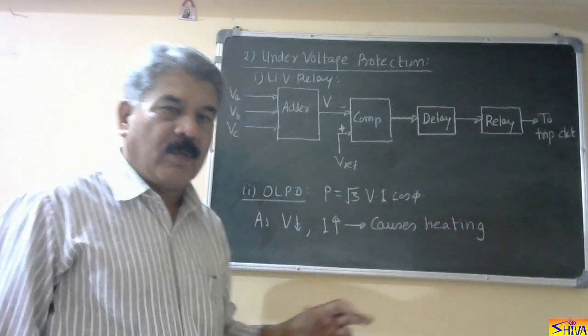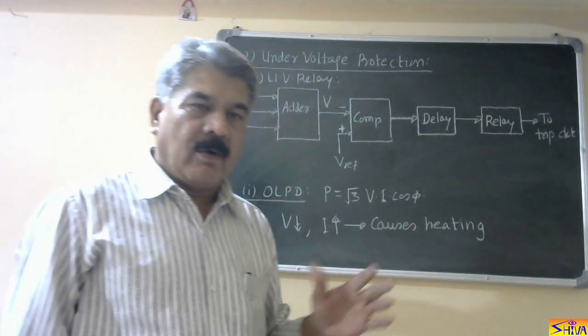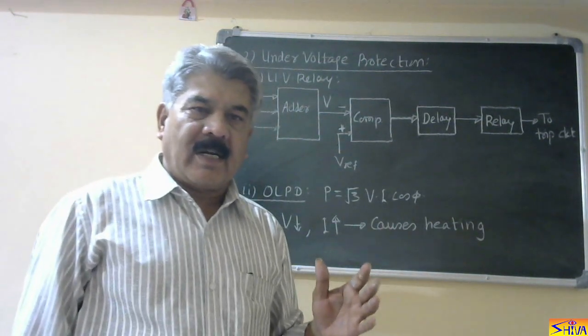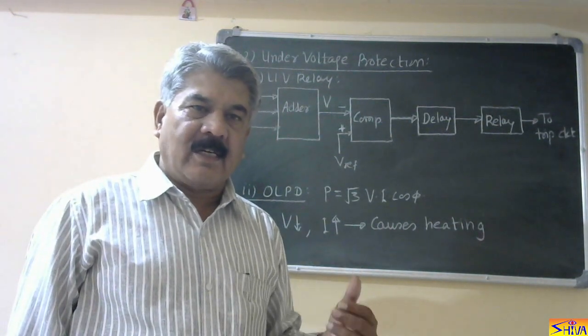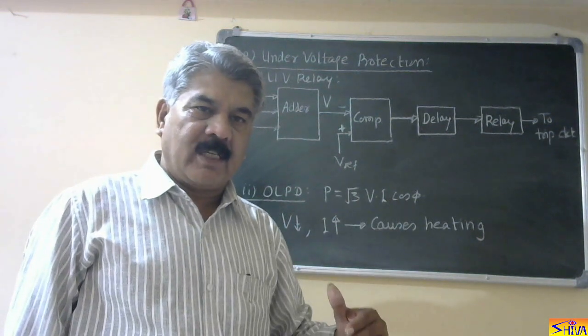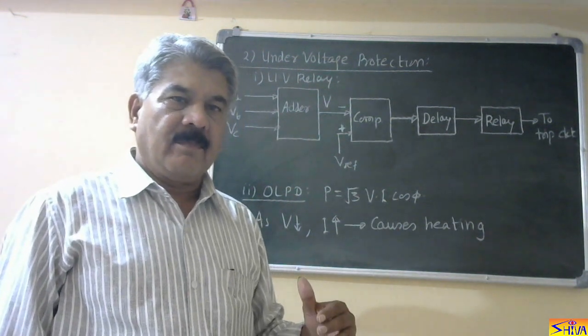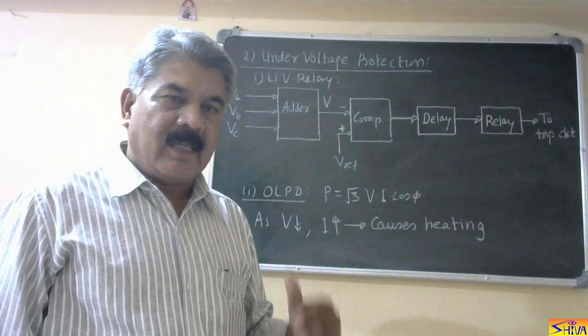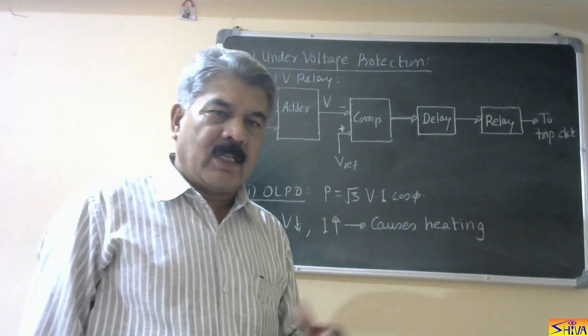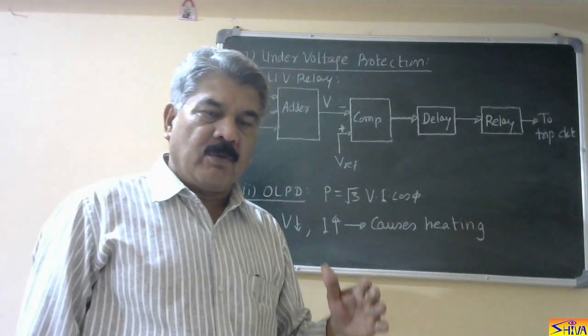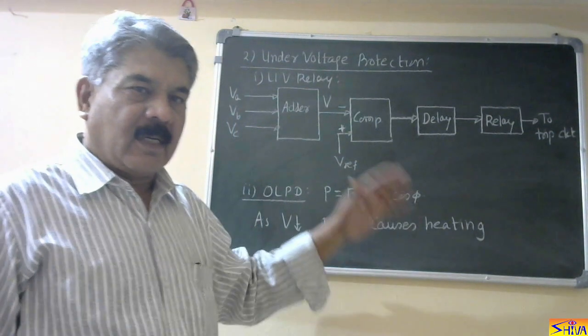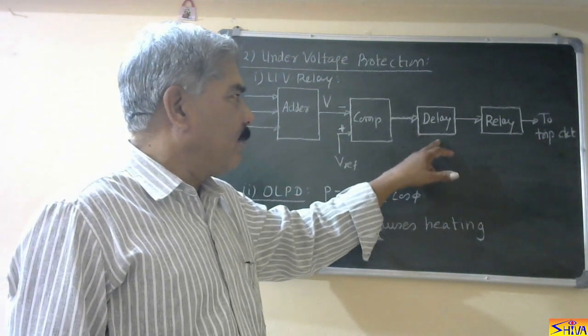Now why are we providing delay for tripping? Because during starting, when the motor draws large current, there is some voltage dip. So during that condition, the relay should not trip. Second thing is, there are always voltage fluctuations for some time. So during these voltage fluctuations also, the relay should not trip. Therefore, we are providing some delay.